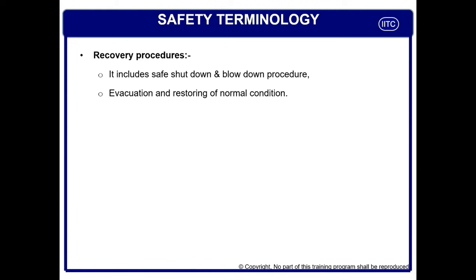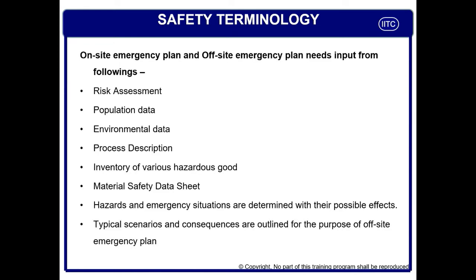There are some recovery procedures which include the safe shutdown and safe blowdown of your plant. Why safe shutdown? Because sometimes when you push the button to stop your operation, it has to be shut down safely. Otherwise, this can create a runaway reaction, over-pressurization, loss of primary containment, and can lead to major fire, major explosion, and toxic emission. This has to be clearly identified and practiced so that there is no further damage in case of any accident.